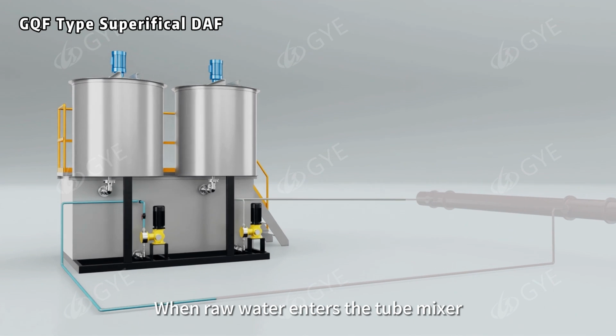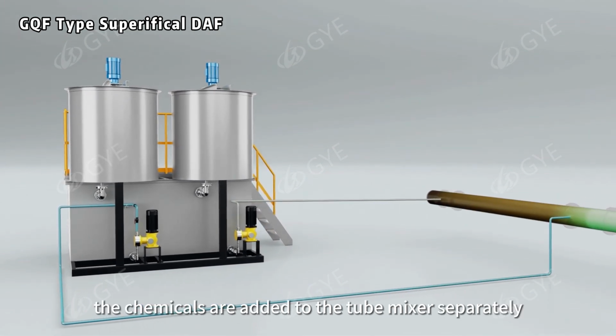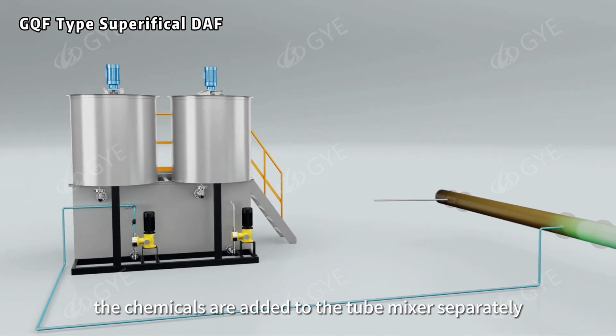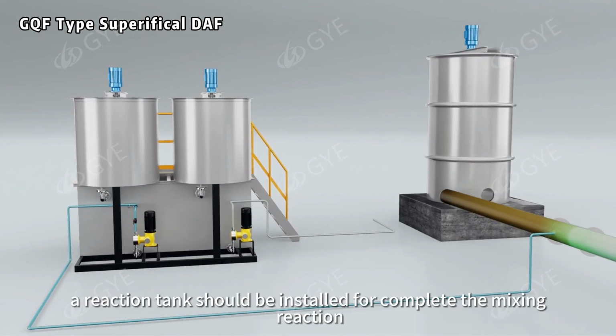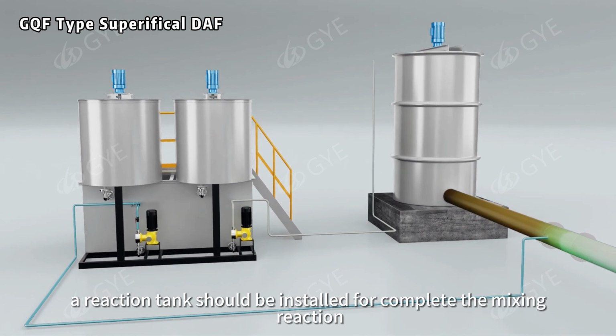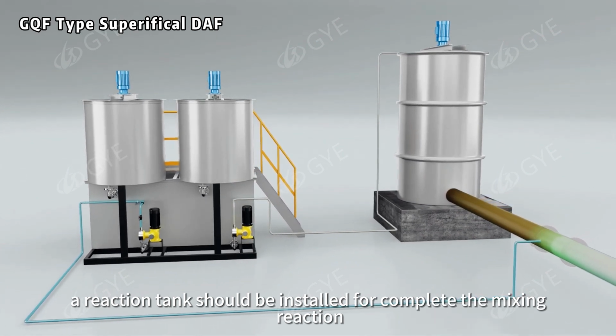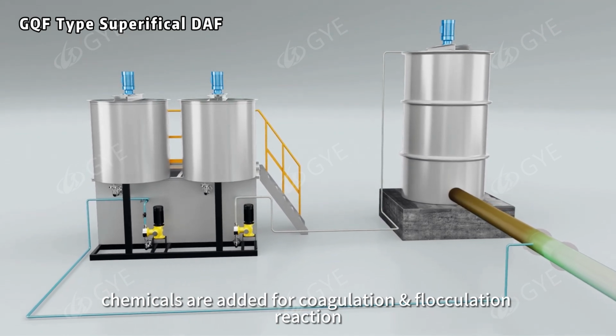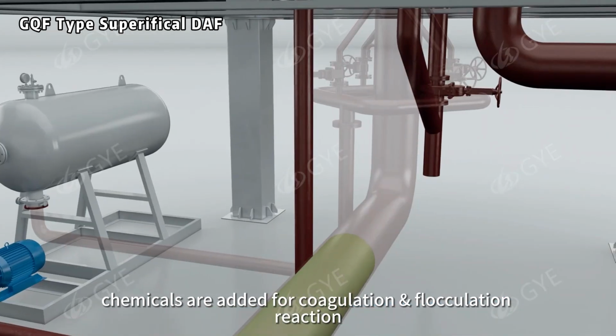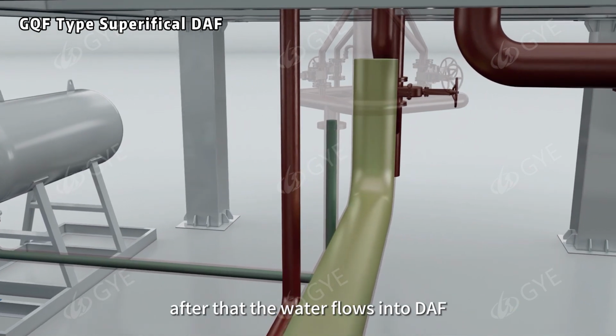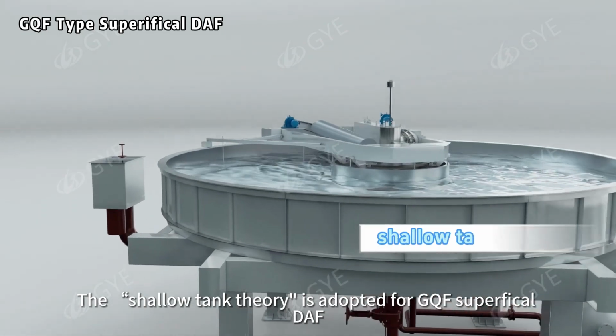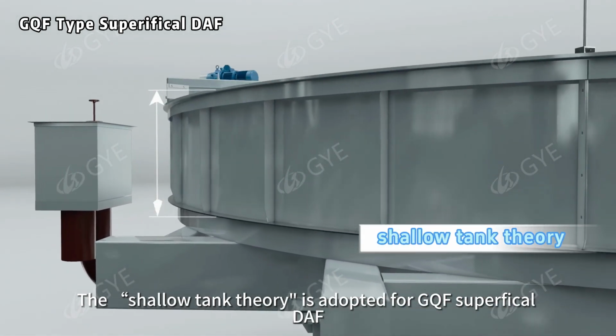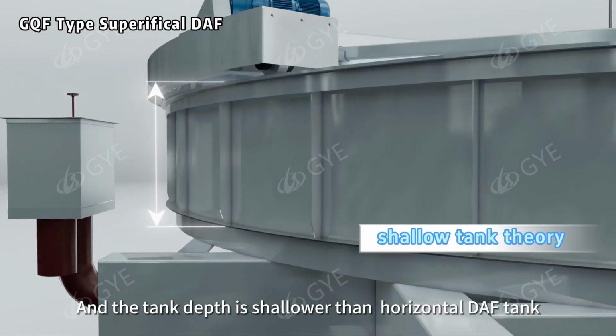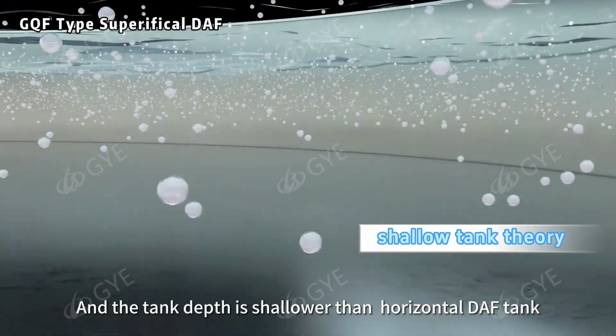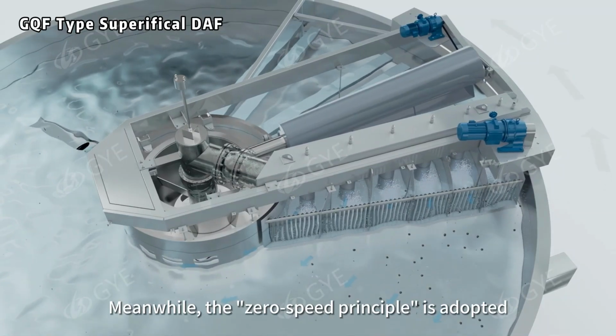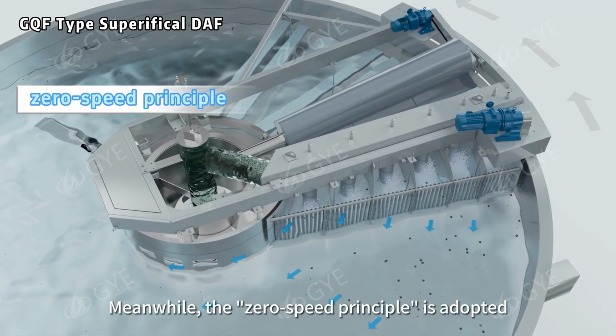When raw water enters the tube mixer, the chemicals are added to the tube mixer separately. If necessary, a reaction tank should be installed to complete the mixing reaction. Chemicals are added for coagulation and flocculation reaction. After that, the water flows into DAF. The shallow tank theory is adopted for GQF superficial DAF, and the tank depth is shallower than horizontal DAF tank. Meanwhile, the zero-speed principle is adopted.